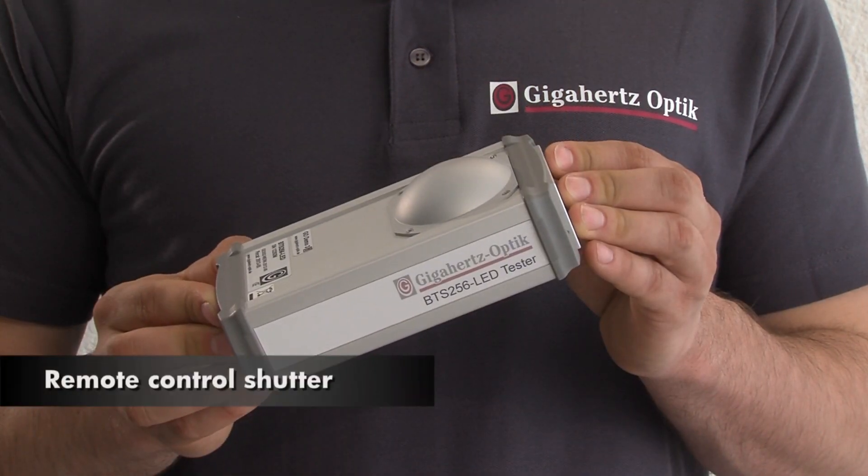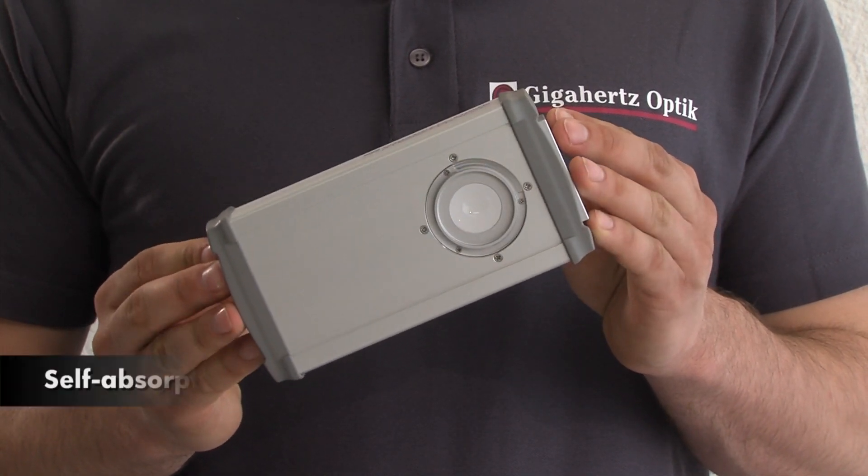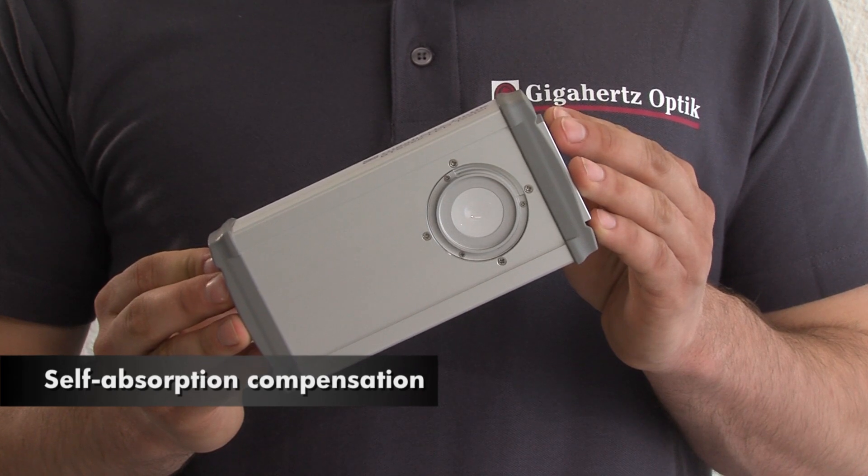An integrated shutter provides dark noise signal compensation of the diode array. Plus, a built-in auxiliary lamp enables self-absorption correction.